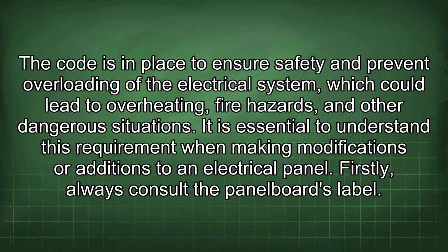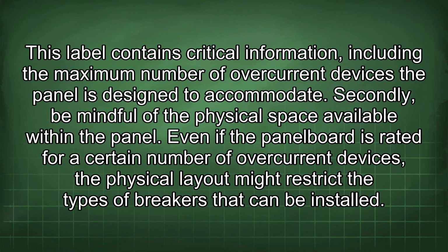The code is in place to ensure safety and prevent overloading of the electrical system, which could lead to overheating, fire hazards, and other dangerous situations. It is essential to understand this requirement when making modifications or additions to an electrical panel. Firstly, always consult the panel board's label. This label contains critical information, including the maximum number of overcurrent devices the panel is designed to accommodate.